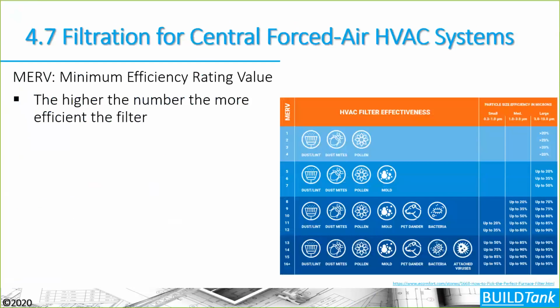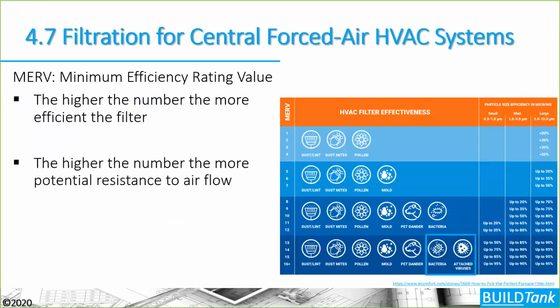MERV stands for minimum efficiency rating value. The higher that MERV number, the more ability that filter has to filter out smaller particles and pollutants in that air. Again, the higher the number, the more resistance to the airflow, however. And that resistance to airflow can cause problems in the distribution of a forced air system.